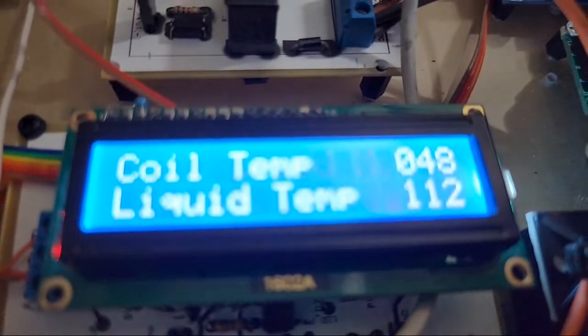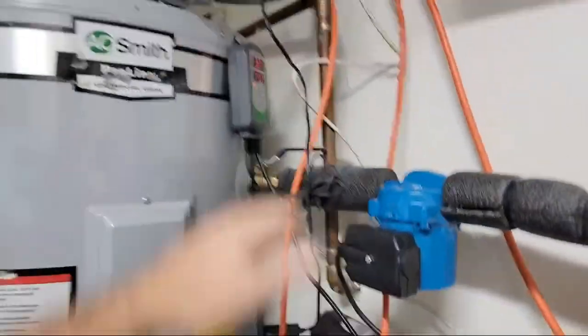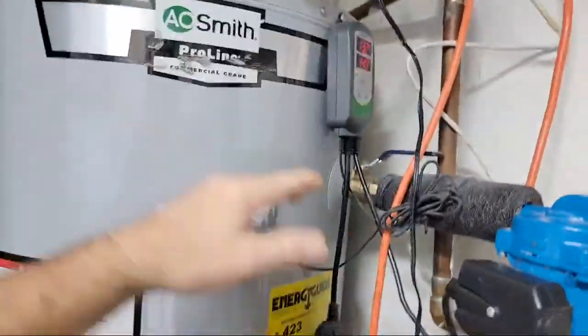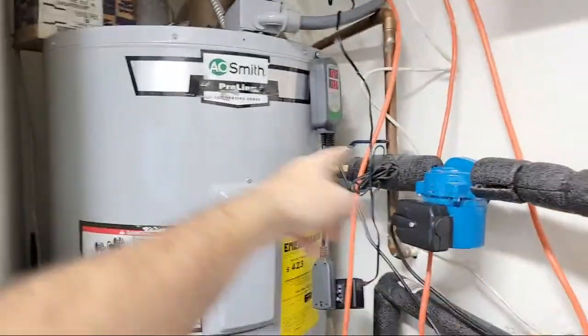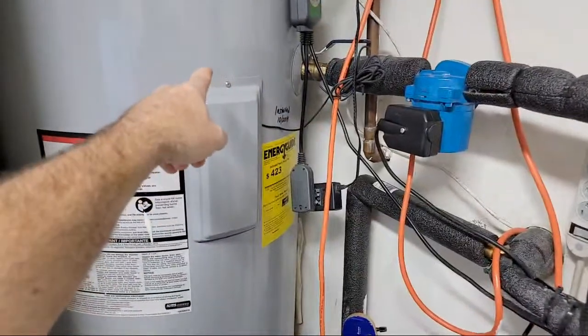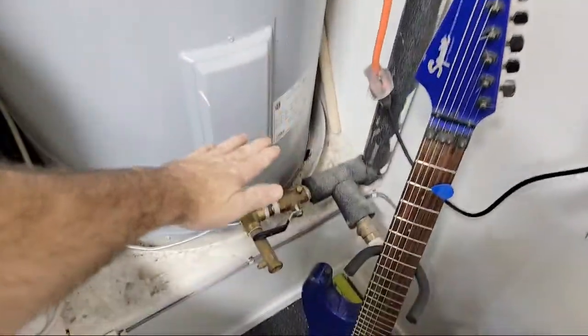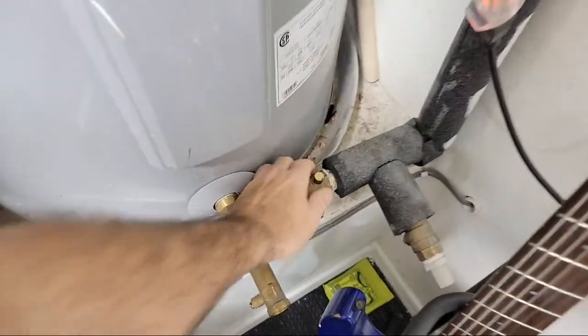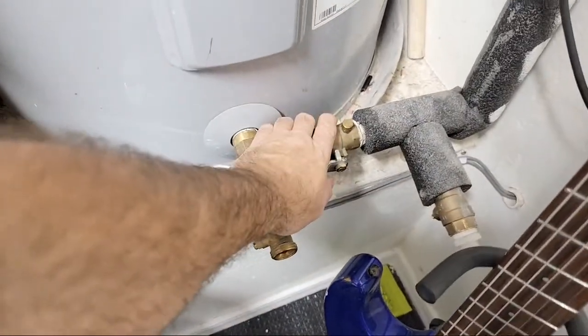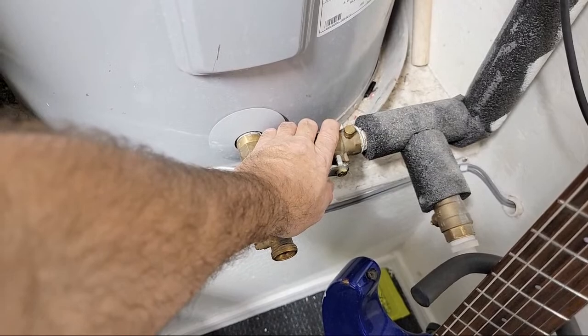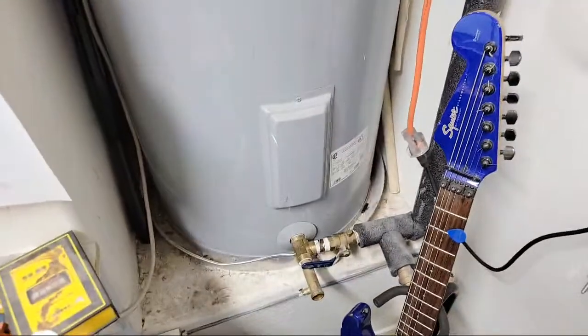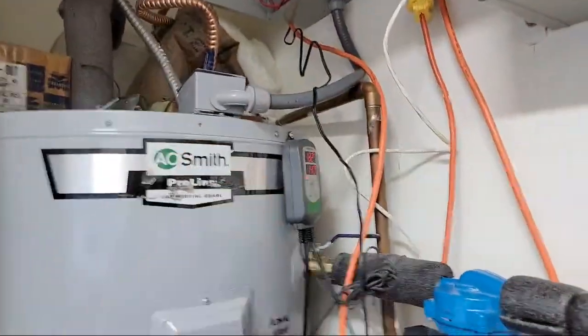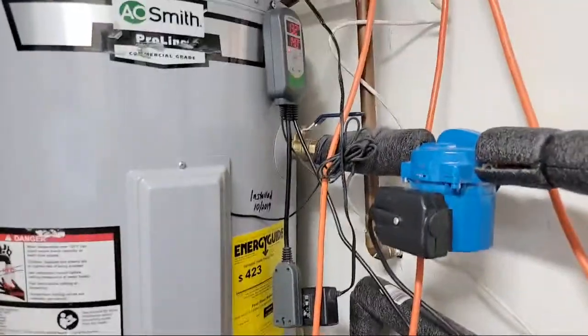Temperatures—see how the liquid line temperature is staying real high, so it's staying happy on high speed now. That's because the whole water heater is full of hot water at this point, because once it keeps pulsing the water back from the low to the top of the tank, eventually the hot water pushes it down into where I no longer feel tap temperature, but hot. And right now I can tell it's almost too hard to hold onto, so it's close to 130, even down there.